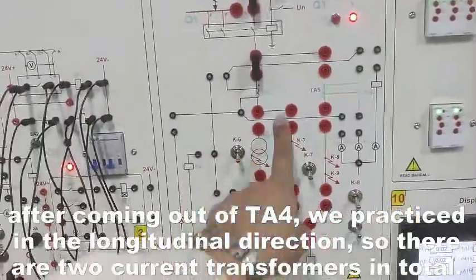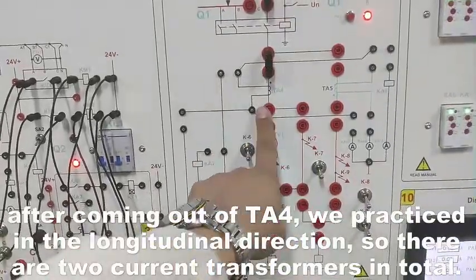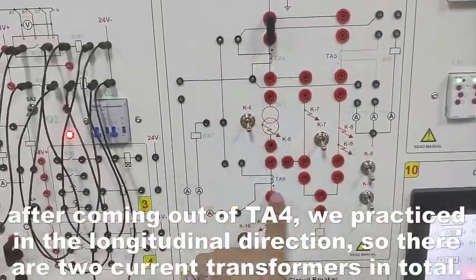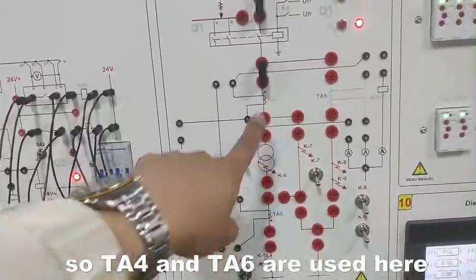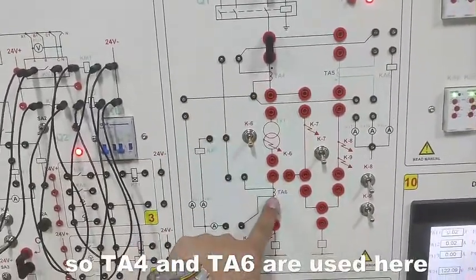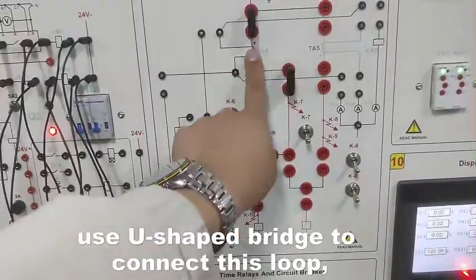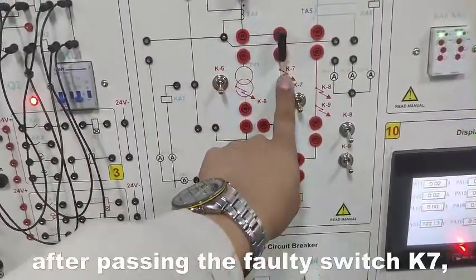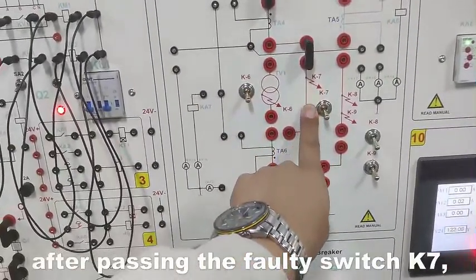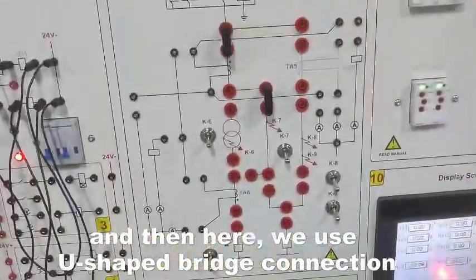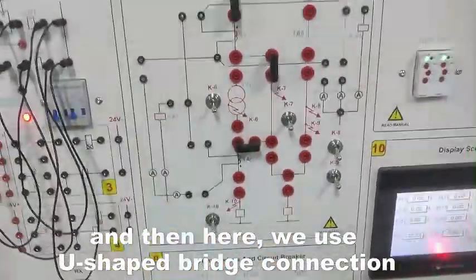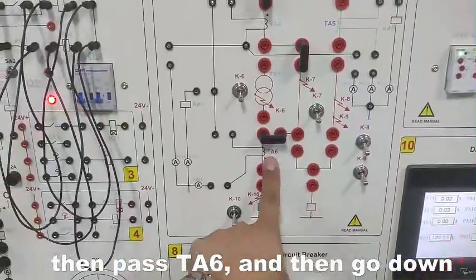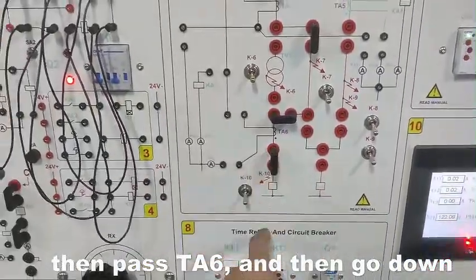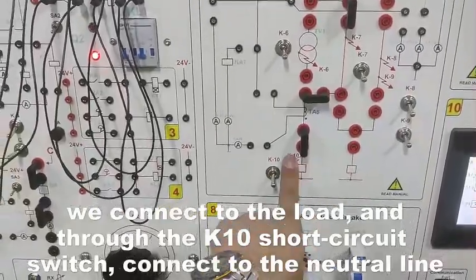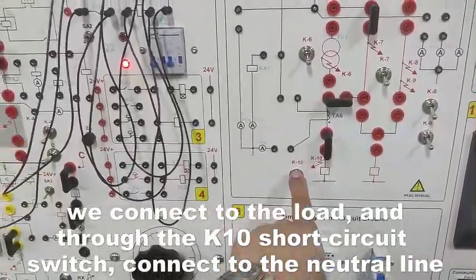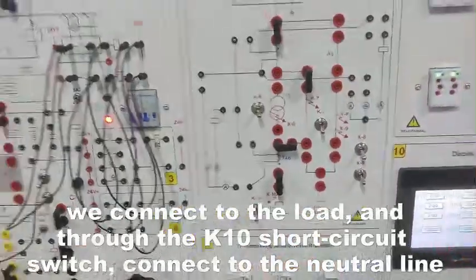After coming out of TA4, we practiced in the longitudinal direction, so there are 2 current transformers in total. So TA4 and TA6 are used here. Use U-shaped bridge to connect this loop. After passing the faulty switch K7, and then here we use U-shaped bridge connection. Then pass TA6 and then go down. We connect the load and through the K10 short circuit switch, connect to the neutral line.